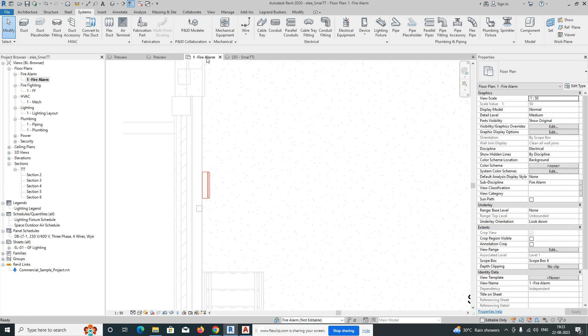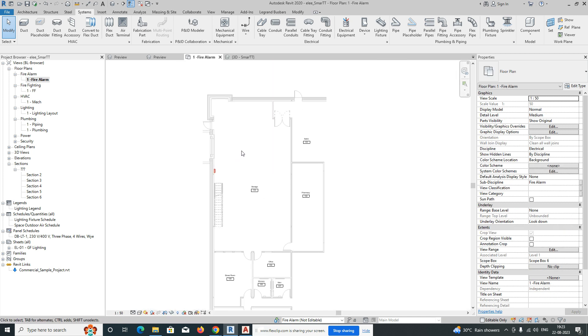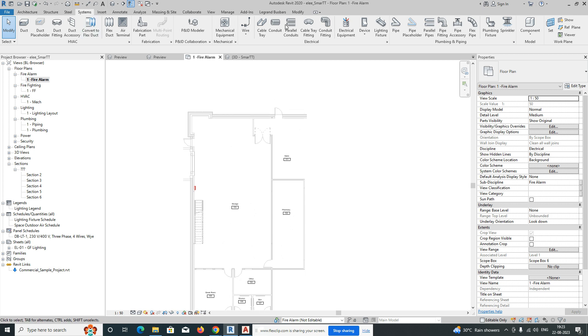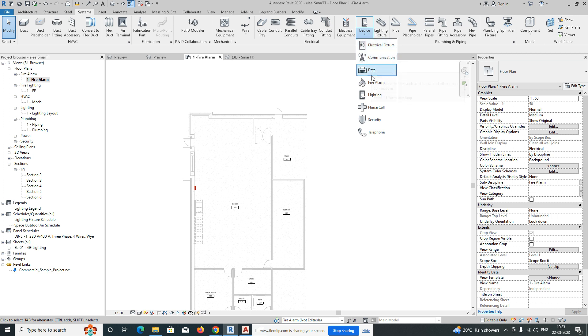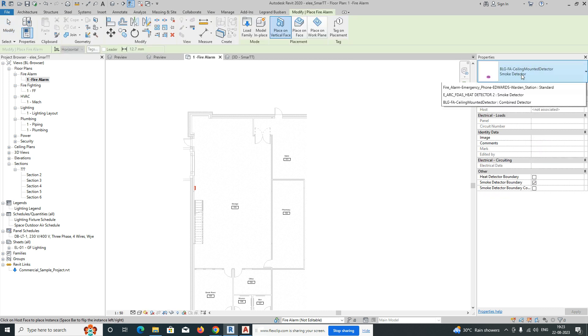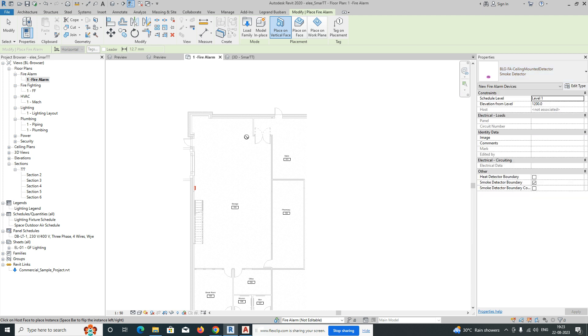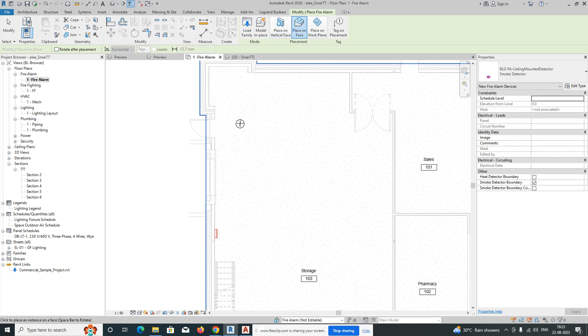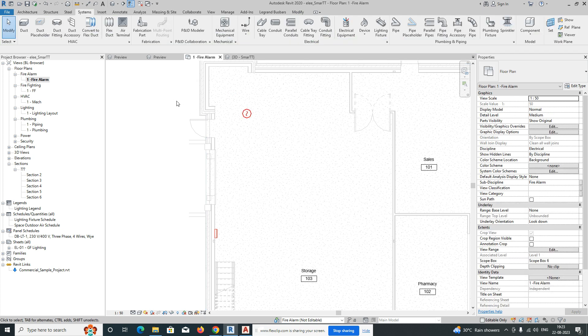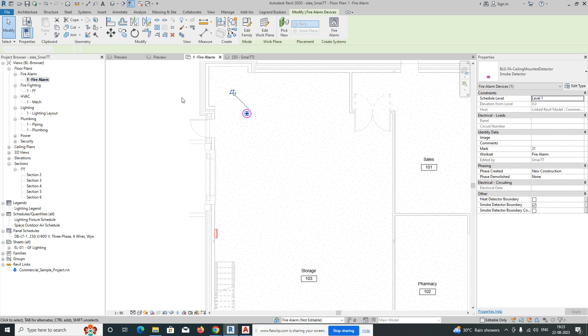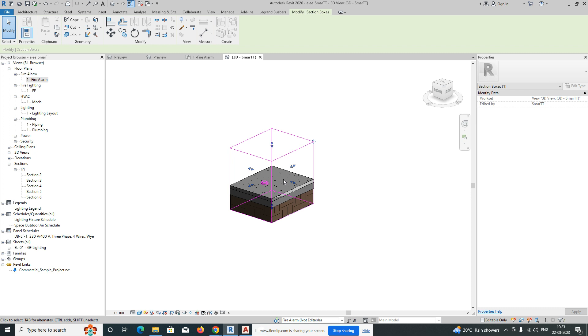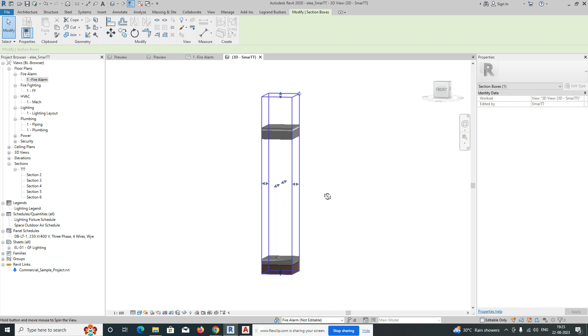Next, we need to place our smoke detectors. Go to the Systems tab again. From the Electrical drop-down panel, select Fire Alarm, and you will see families for fire alarm devices. Choose the smoke detector and set placement to 'Place on Face.' Place one smoke detector on the plan, then go to the 3D view to check how it looks.